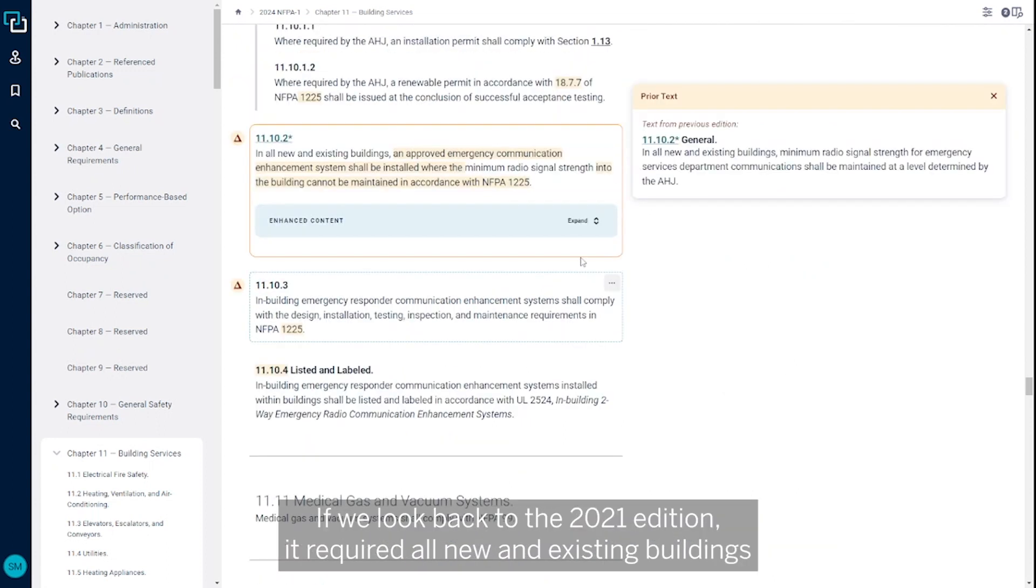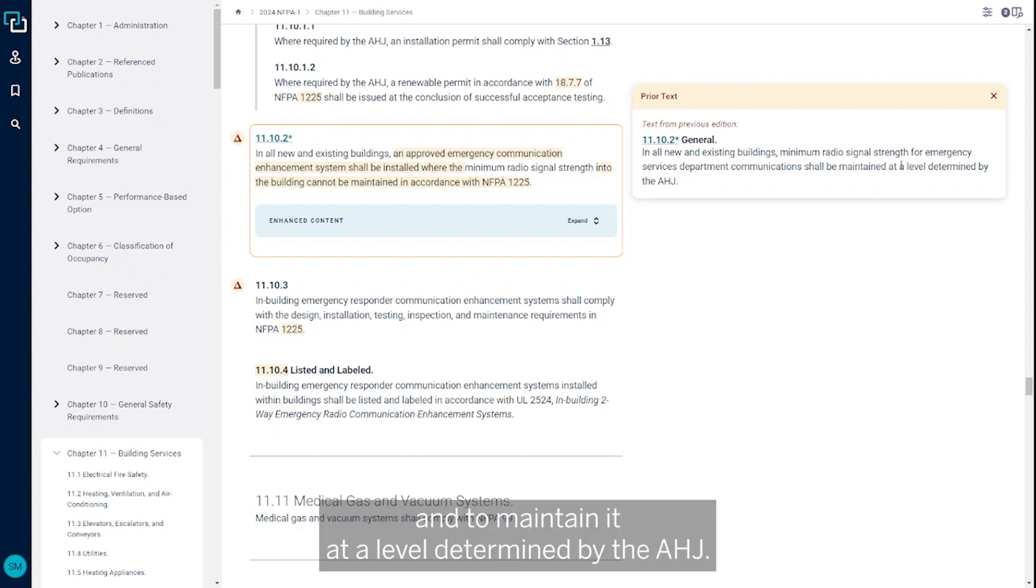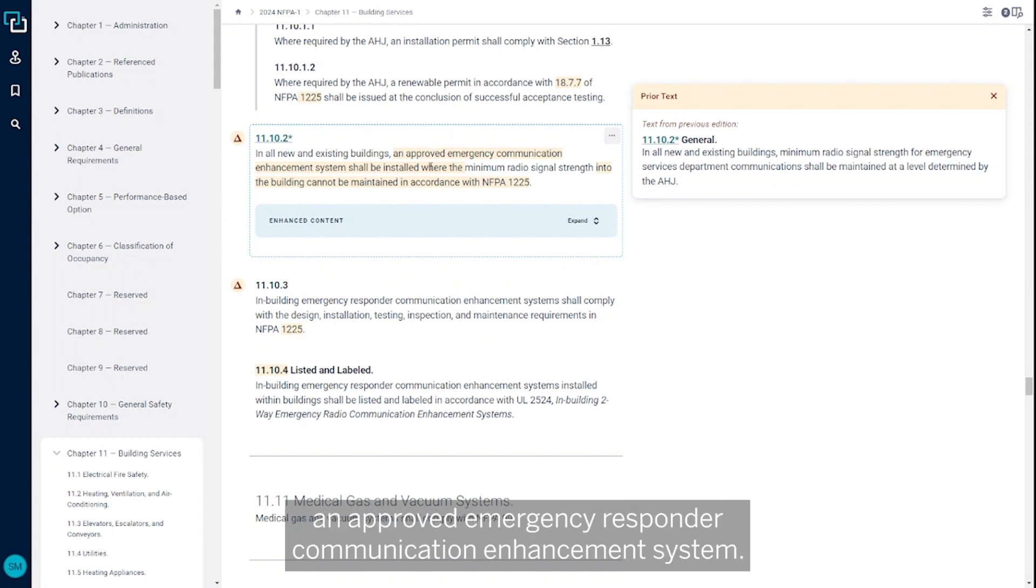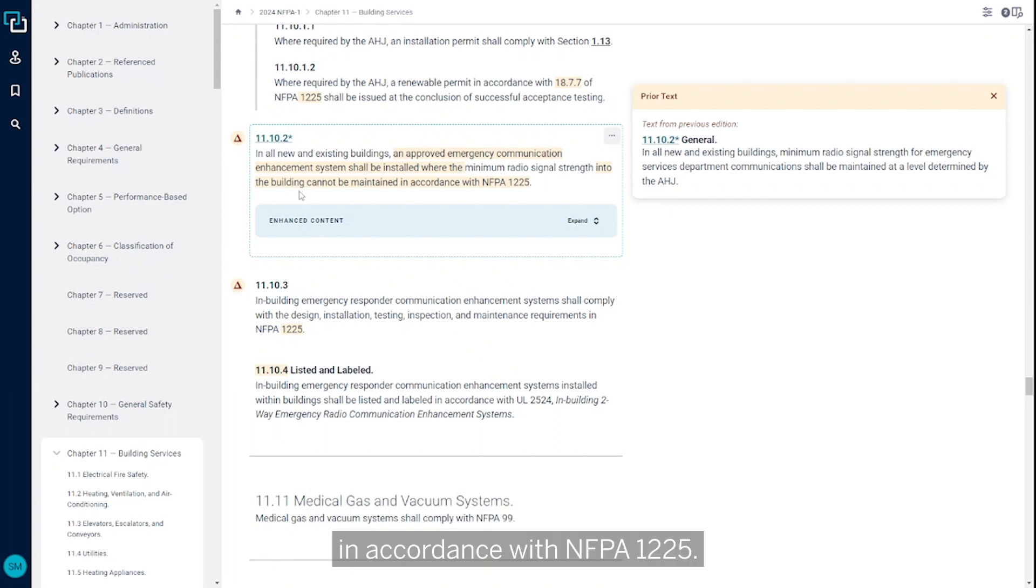it required all new and existing buildings to maintain a minimum radio signal strength for emergency services at a level determined by the AHJ. Now, new and existing buildings need to have an approved emergency responder communication enhancement system if the minimum radio signal strength cannot be maintained in accordance with NFPA 1225.